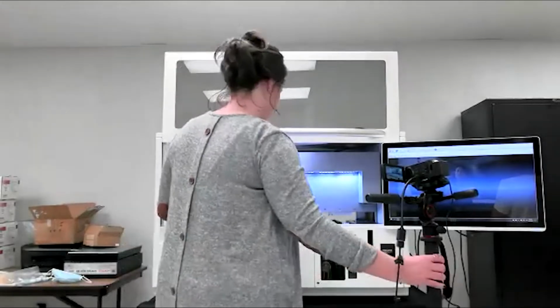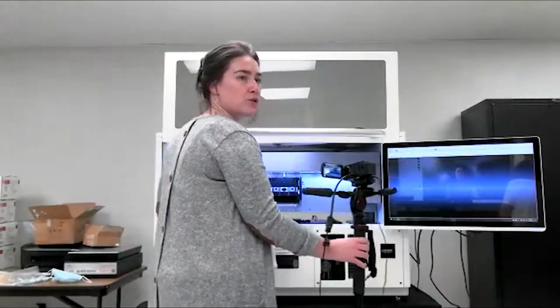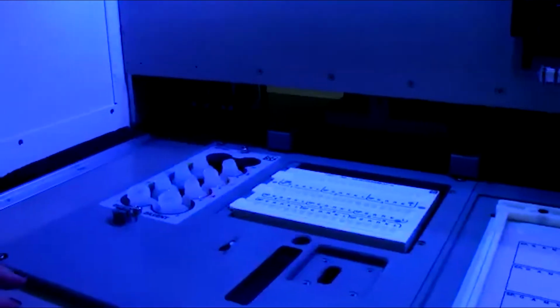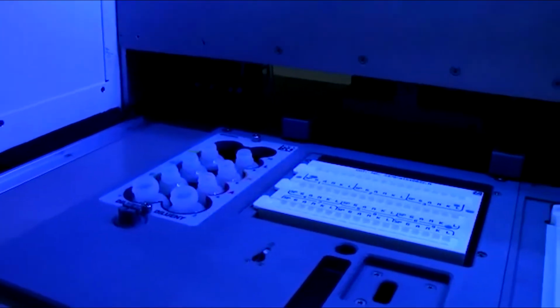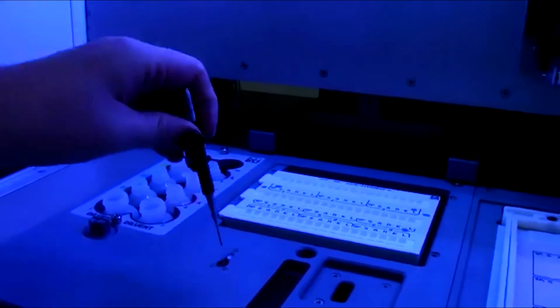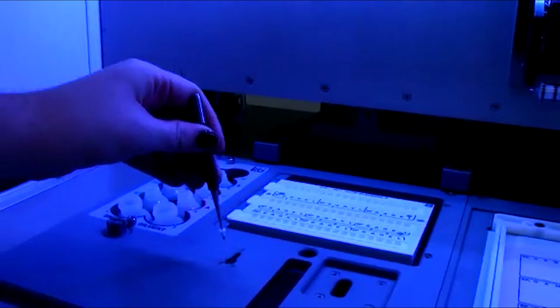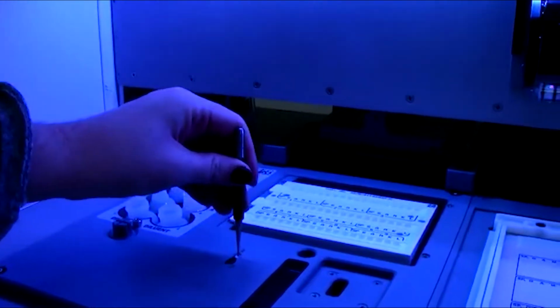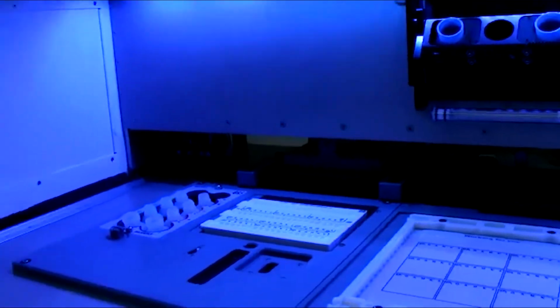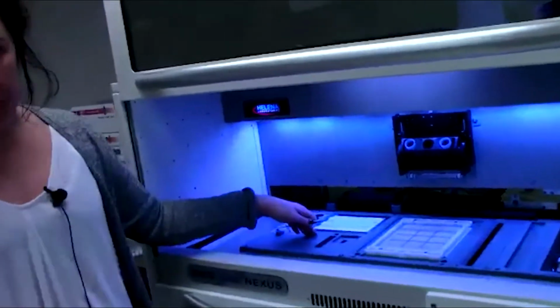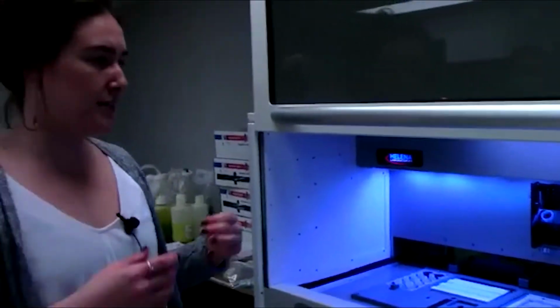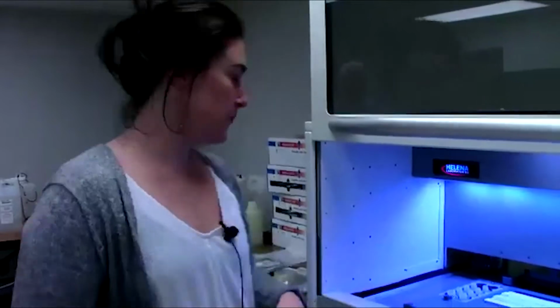You'll also notice that that spreader tip is in position. There is a spreader tip tool. You'll have to install this before the first time you run, but afterwards it'll just stay in position. So that spreader tip tool puts that in there. The SPIFE Nexus will alert you for most pieces that are missing. So if you try to start a run and you don't have your dryer cover installed, or if you have it installed incorrectly, or if you don't have your spreader tip installed, it will alert you to all of those things so that you have a chance to correct that before the run begins.